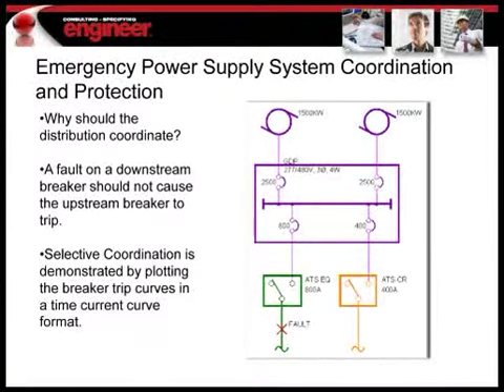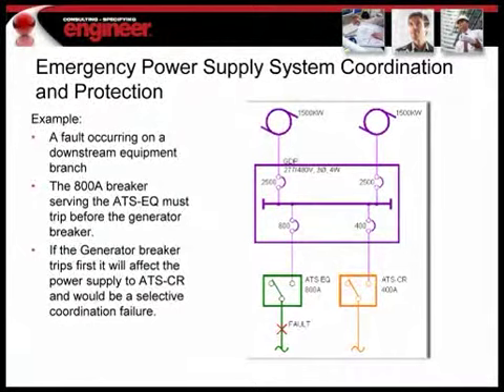So what we're looking at here is, if we had a fault on the load side of ATS EQ, we would want the breaker that feeds ATS EQ to react first before the generator breaker reacts. If the generator breaker were the one that picks it up, it obviously would affect ATS CR. The way that we demonstrate selective coordination is by putting all these breakers onto a time current curve format and showing how that plots. We do go into a couple of those curves later on in the presentation.